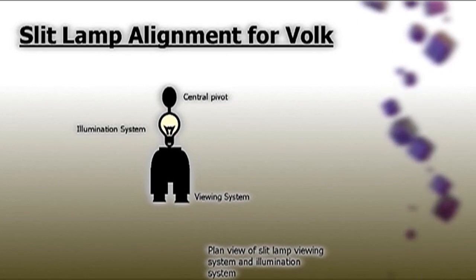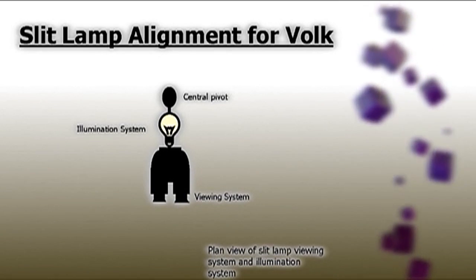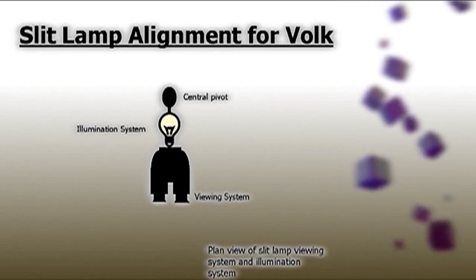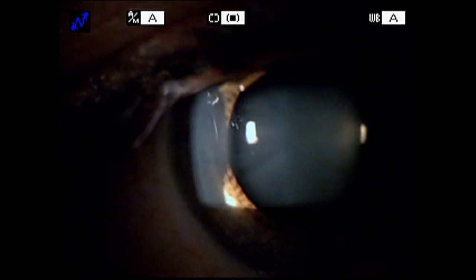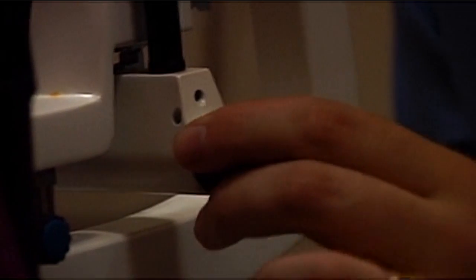We then need to make sure the illumination and viewing system are perfectly in line, one behind the other. We would use a parallelepiped beam, usually 2mm in width and with a height that matches the pupil height. We tend to set the magnification to around 10 times to start the Volk assessment.